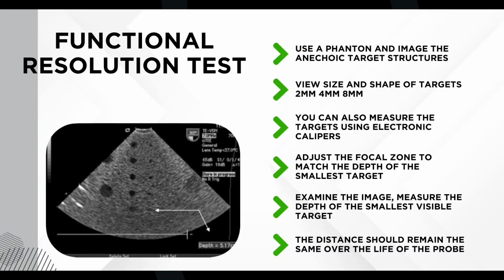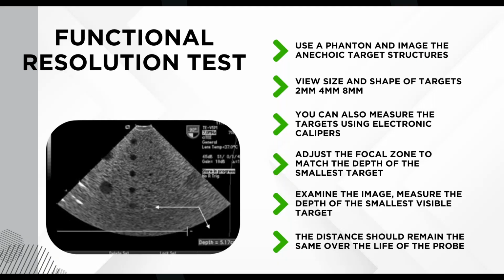If you saw any change or degradation over time, with this being a linear transducer, 12 linear, higher frequency, less depth of penetration here. If I started to see less, maybe 3 centimeters or 2 centimeters here in this area, then I would say that this transducer is probably going bad, and there could be an issue with it in the future, or there is an issue with it at that particular point in time. All right, where are we at next? This guy. So we're going to functional resolution test.